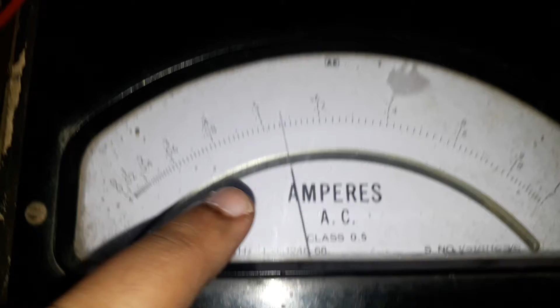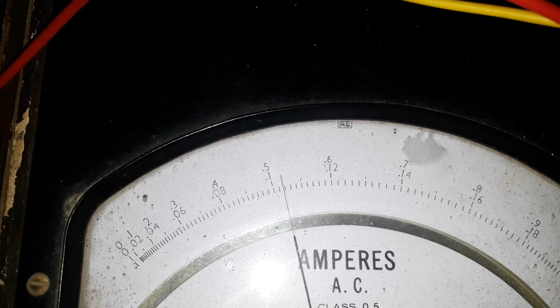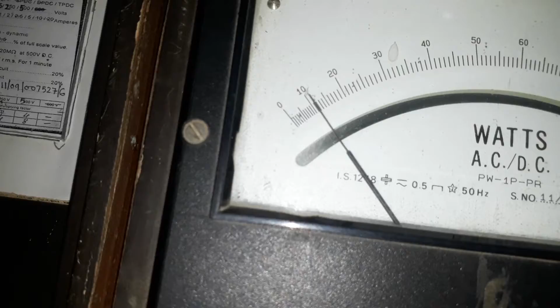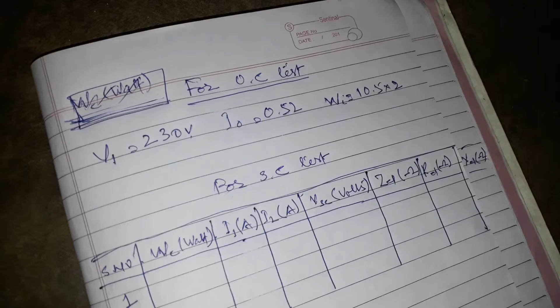Now corresponding to this voltage, you note down this voltage. This is the open circuit voltage. Corresponding to this, we will note down the current. It is connected in the 0 to 1 ampere range, which is the uppermost. It is wobbling slightly, around 0.52. So the current is 0.52 and the wattmeter reading is approximately 10.5 watts, and the multiplying factor which we have already determined is 2, so multiplied by 2, 21. So these are all the readings which we have to collect for the first set of experimentation.